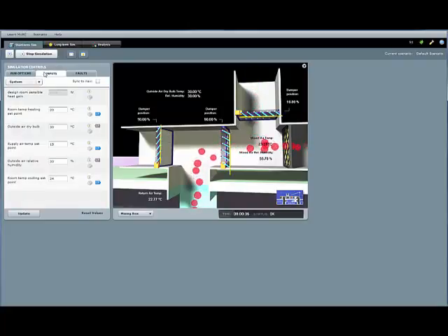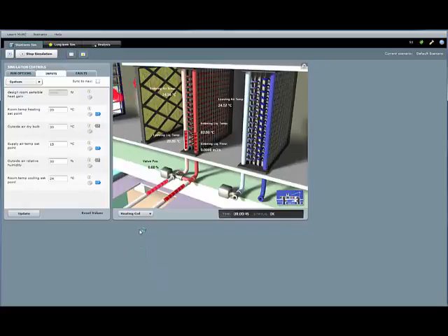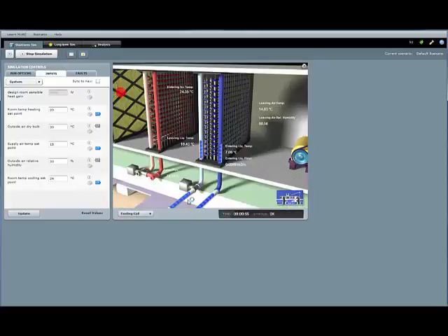It has been started, and the pink or red balls show hot air, blue show cool air, and the colors change accordingly. Here we see the incoming air at about 24 degrees C coming through the heating coil, which doesn't need to operate, but we're going to the cooling coil, and we want the air to be more like 15 degrees C coming into the space.